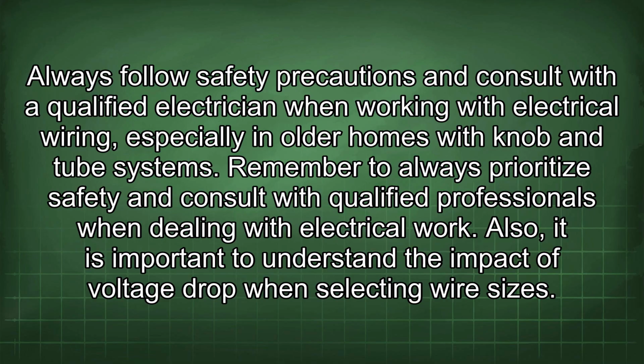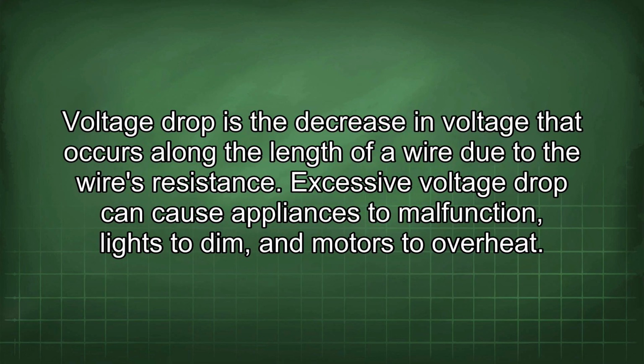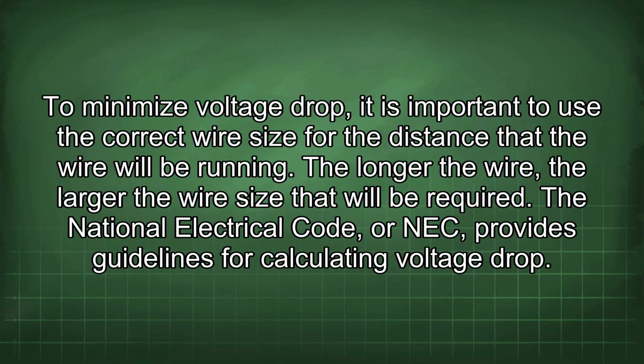Also, it is important to understand the impact of voltage drop when selecting wire sizes. Voltage drop is the decrease in voltage that occurs along the length of a wire due to the wire's resistance. Excessive voltage drop can cause appliances to malfunction, lights to dim, and motors to overheat. To minimize voltage drop, it is important to use the correct wire size for the distance that the wire will be running. The longer the wire, the larger the wire size that will be required.